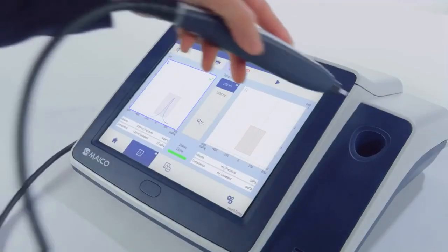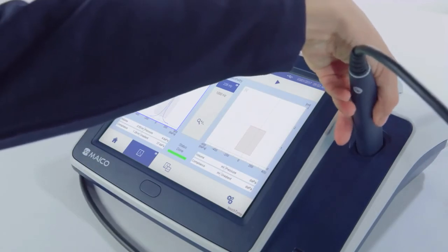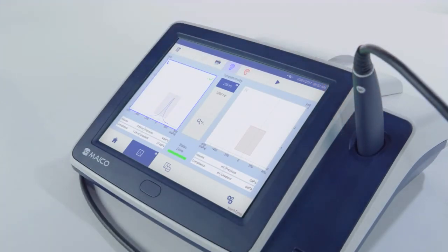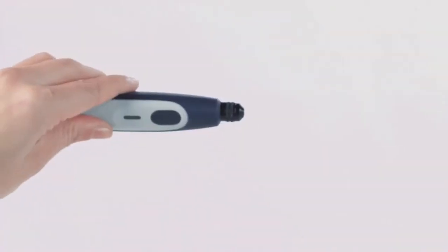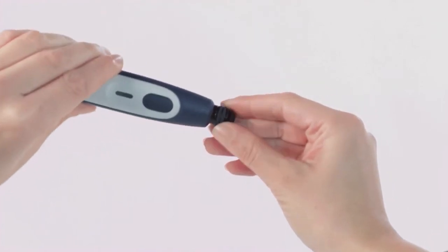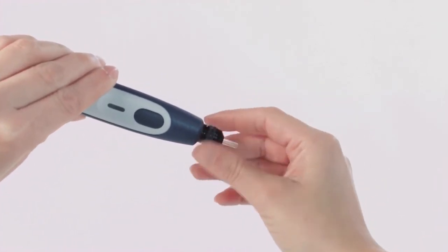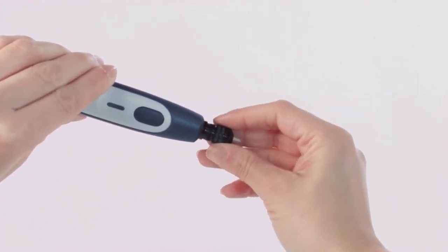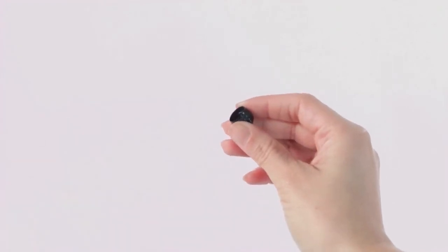After successful completion of a test, place the probe into the cavity and the results will print automatically. This function is only enabled when the device is purchased with an integrated printer. To clean the probe tip, first unscrew the probe cap by turning it in a counterclockwise direction. Never clean the probe tip while the tip is still attached to the probe.